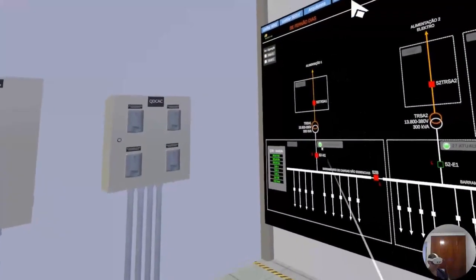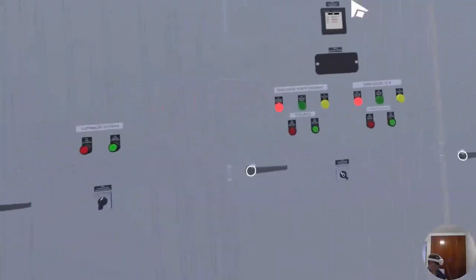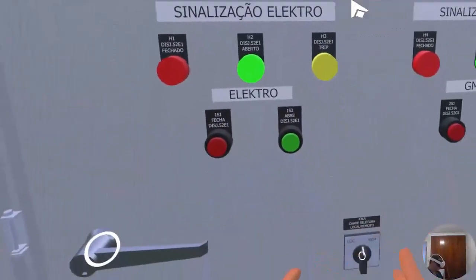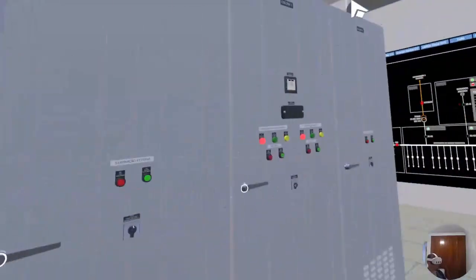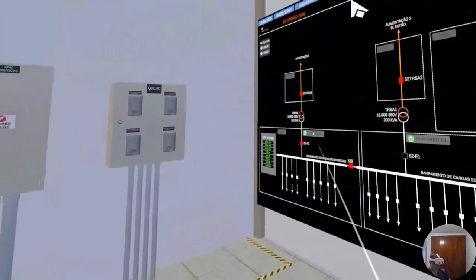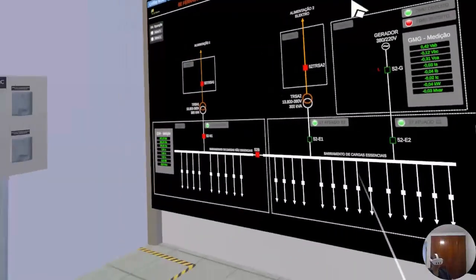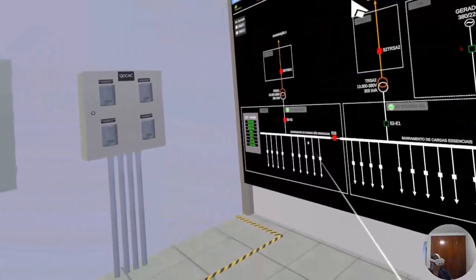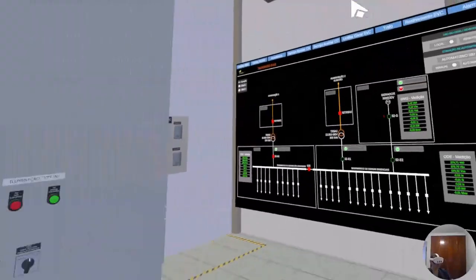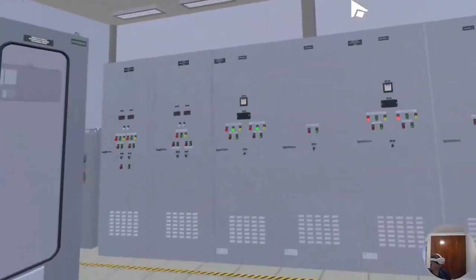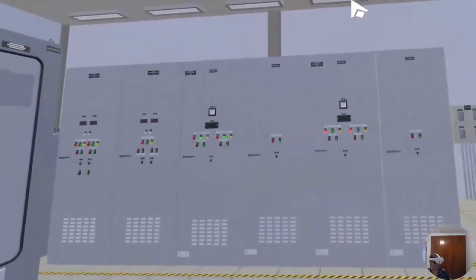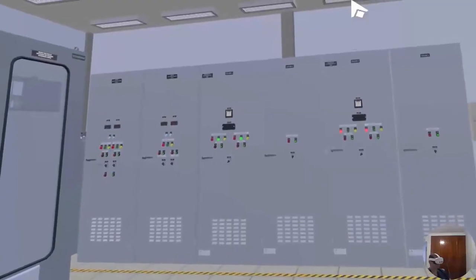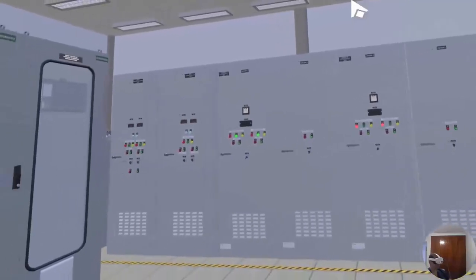Finally, to complete my normalization process, turn my switches back to remote mode, in case I need to remotely operate these circuit breakers later on. So system normalized with voltage, essential loads energized, non-essential loads also energized. So that's it, guys. This is how you operate a substation's auxiliary service, considering it's in manual mode, entirely in the hands of the operations team.